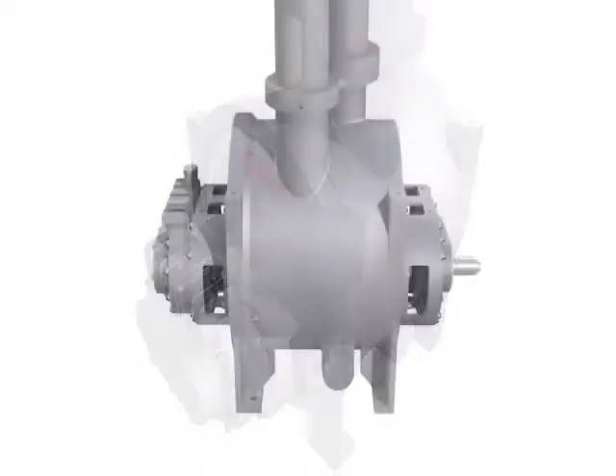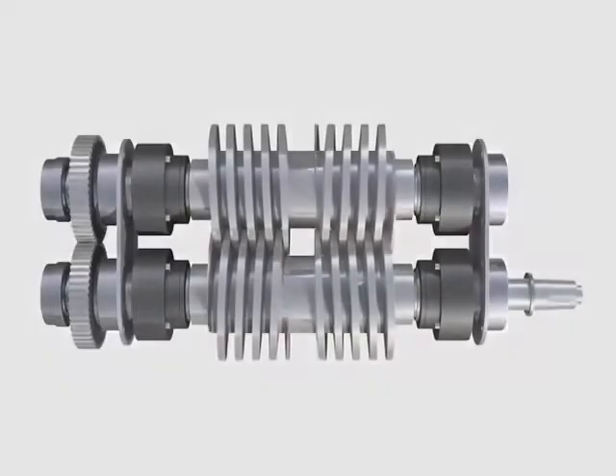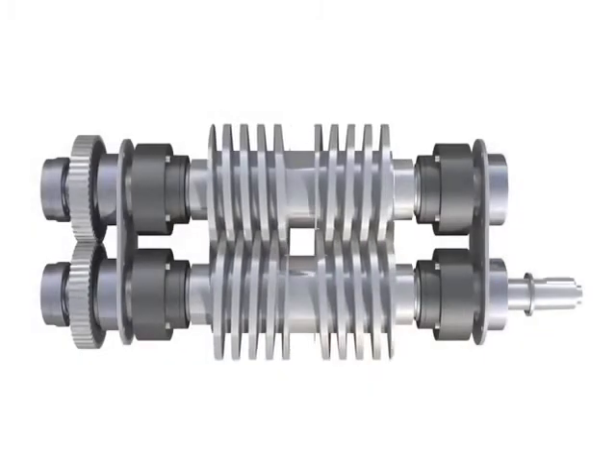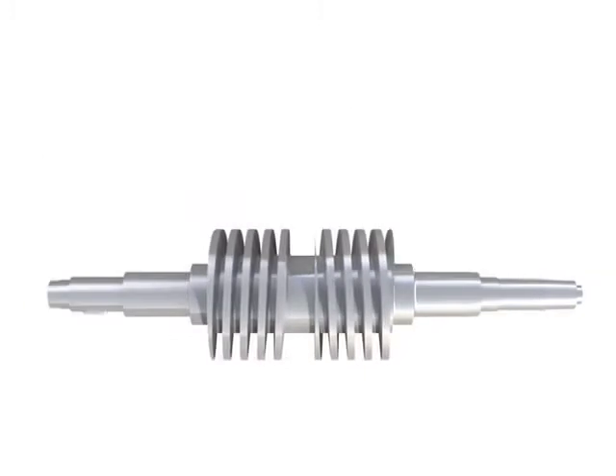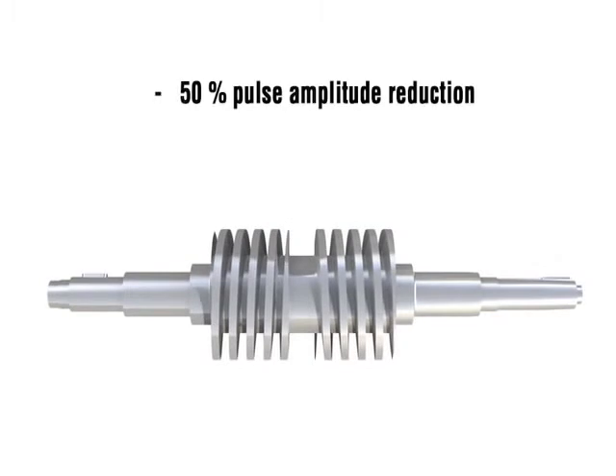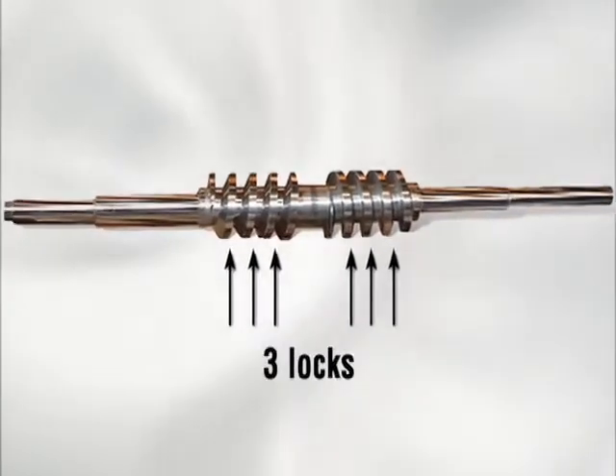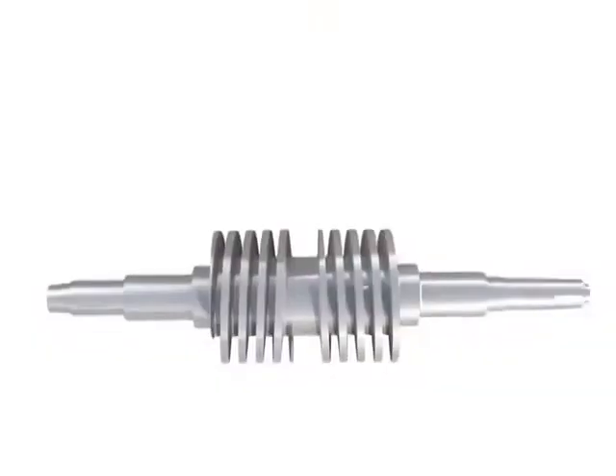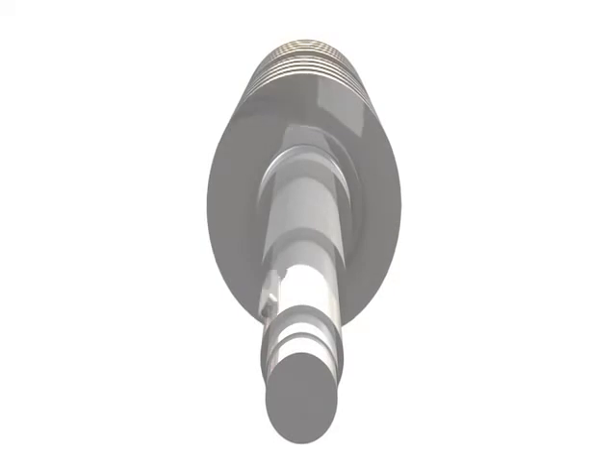The FlowServe MP1 is built with a one-piece integral rotor, offering greater shaft strength and high torque handling capability when compared with multi-piece rotor designs. Robust radial bearings at each end of the shaft support full hydraulic loading, even at 100% gas operation when the hydrodynamic fluid film is not present for radial load support. The screws are designed to deliver extremely low pulse amplitudes and vibration levels. Each opposing screw lead is designed to contain a minimum of three locks that enable the pressure profile to be developed gradually, while minimizing pressure pulsations and vibration.